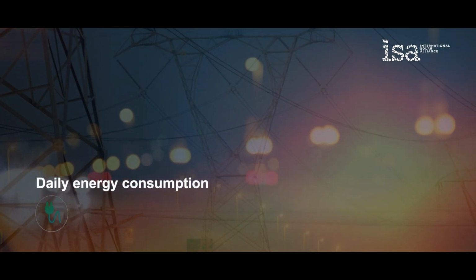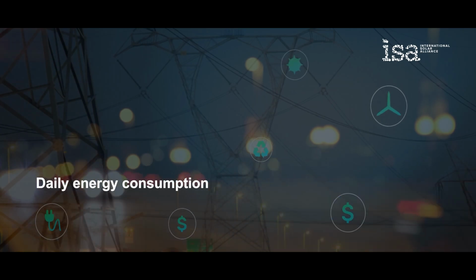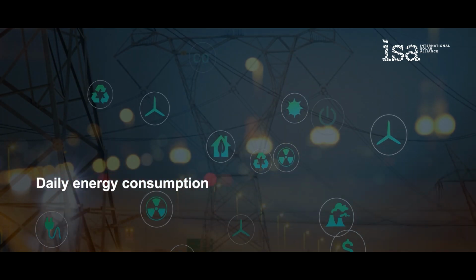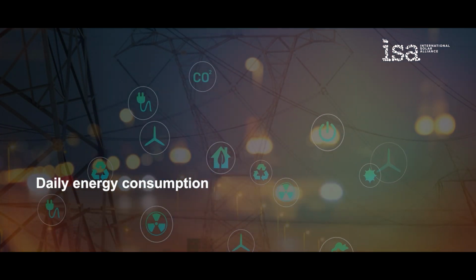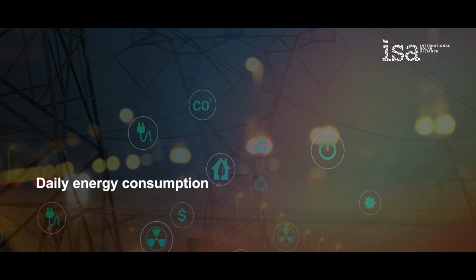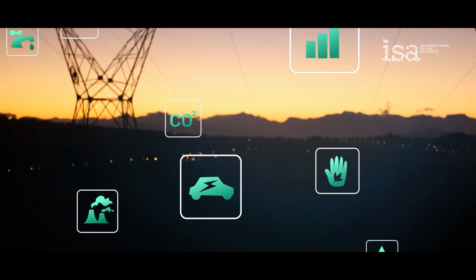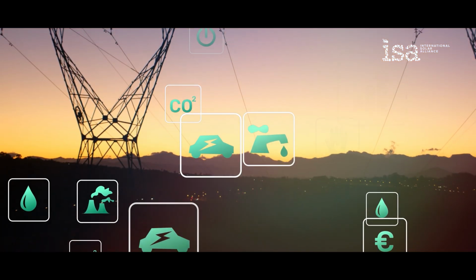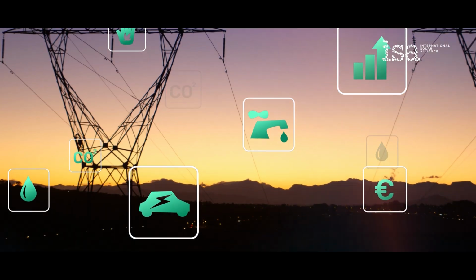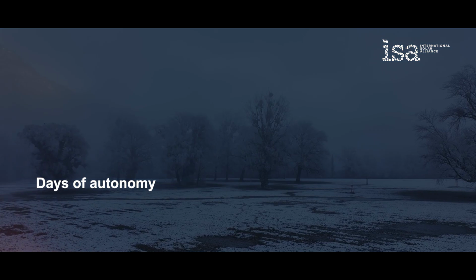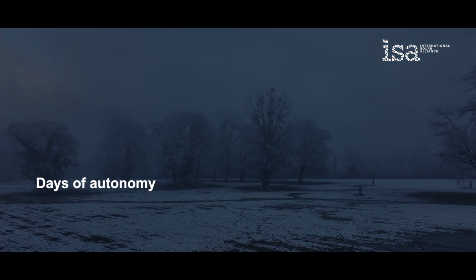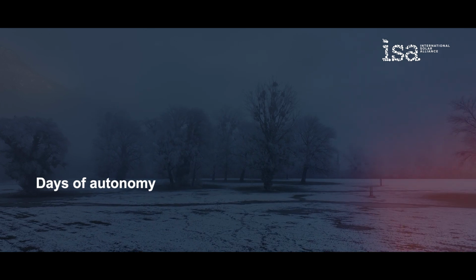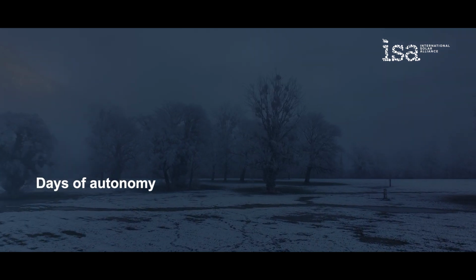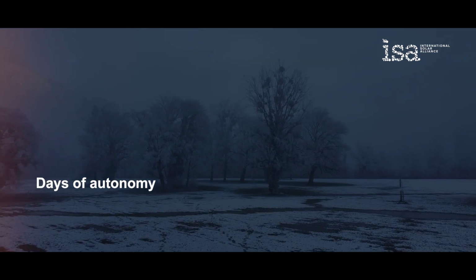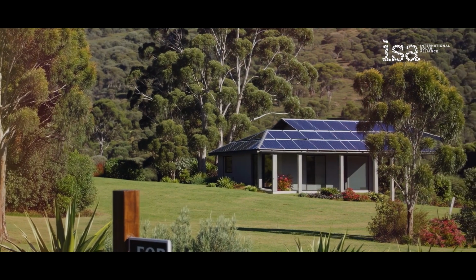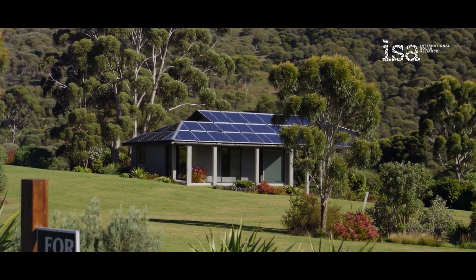Daily energy consumption: this is the most critical factor, representing your total daily energy consumption in kilowatt hours (kWh) that needs to be met from the batteries. You must calculate this to know the minimum amount of energy the battery needs to store to meet your needs on a daily basis. Days of autonomy refers to how many days you want your system to run without any solar input. A higher number of days, for example 2 to 3 days standard for off-grid, requires a larger battery capacity.